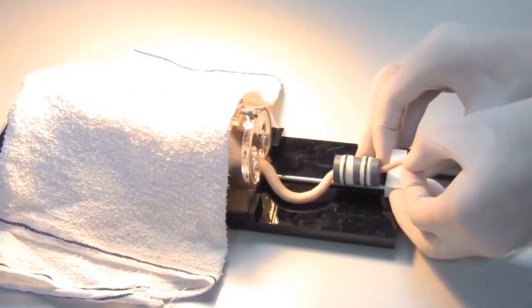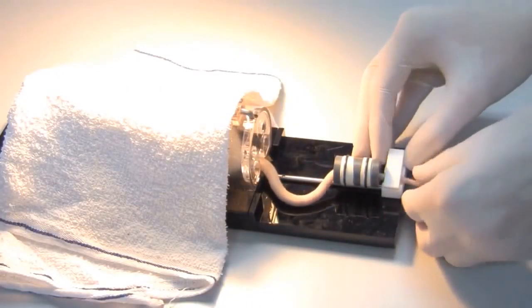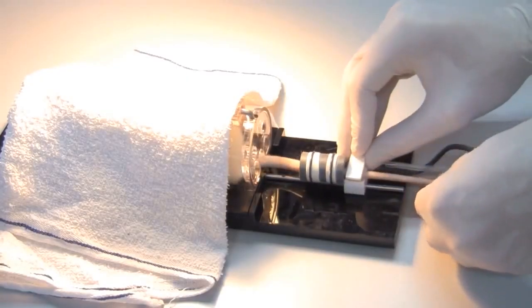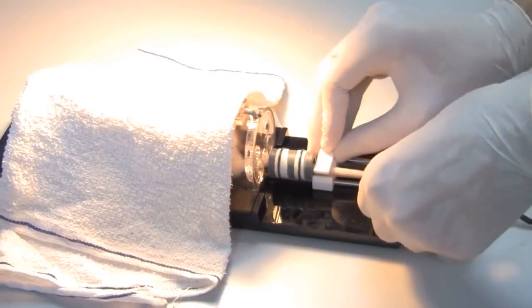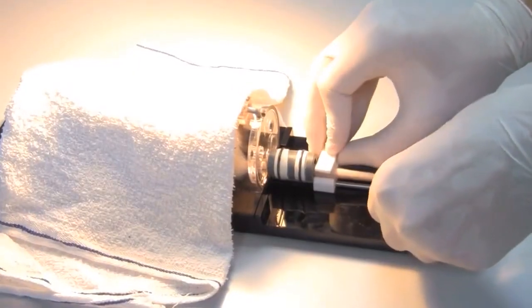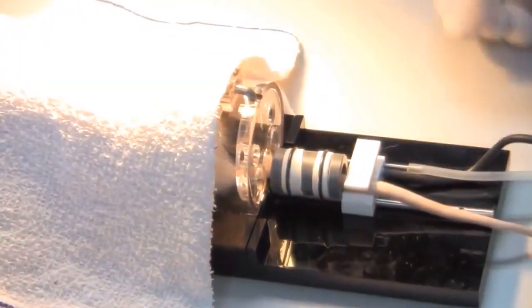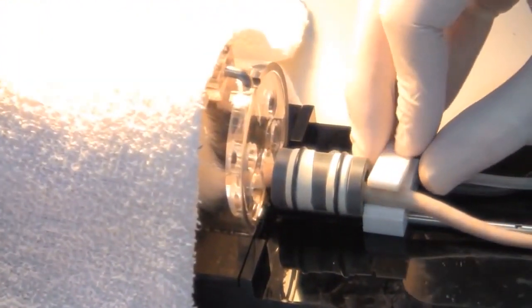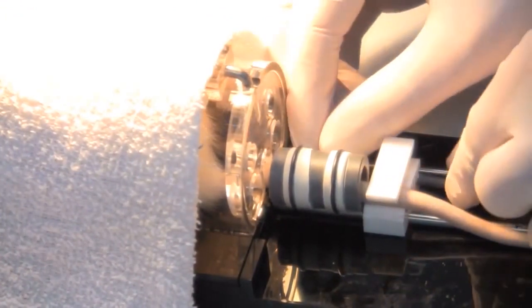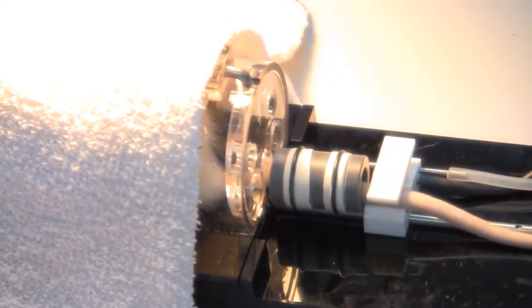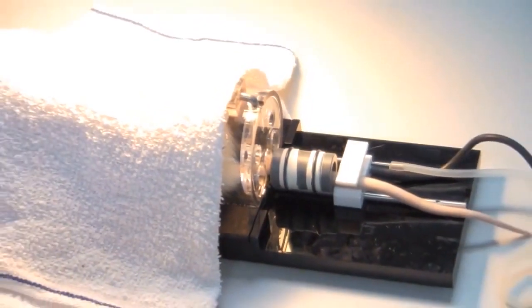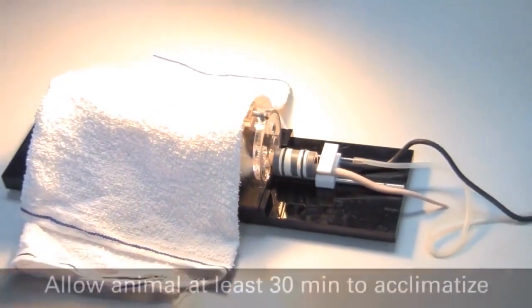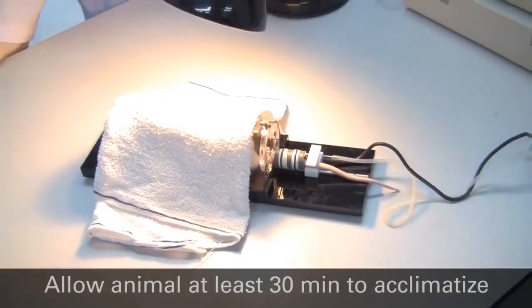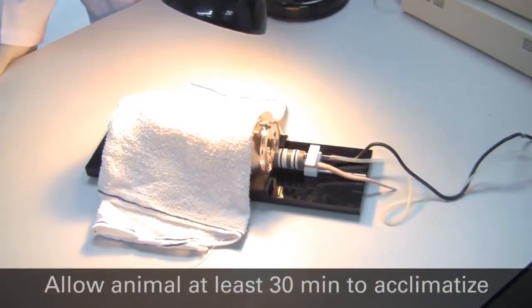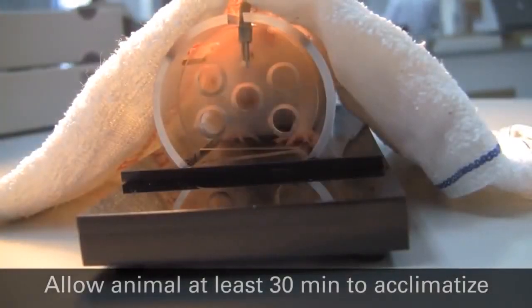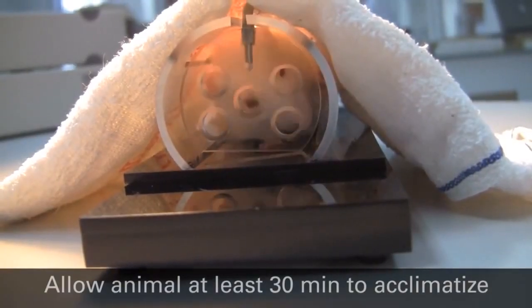The tail cuff is slid over the subject's tail along the tail cuff holder until it rests closely to the tail end of the restrainer. The tail is also placed securely within the pulse transducer. Once secured, ensure that the pulse transducer is not in contact with the tail cuff, as vibrations from the cuff may affect the pulse signal. It is recommended that the subject is allowed to acclimatize to its new surroundings for at least 30 minutes prior to acquiring any data.